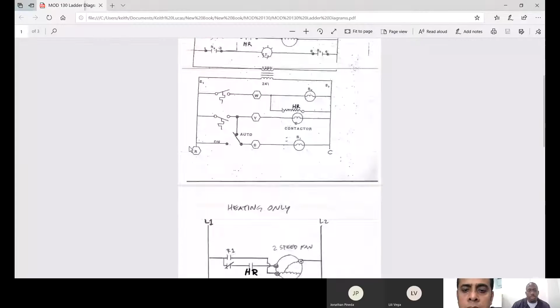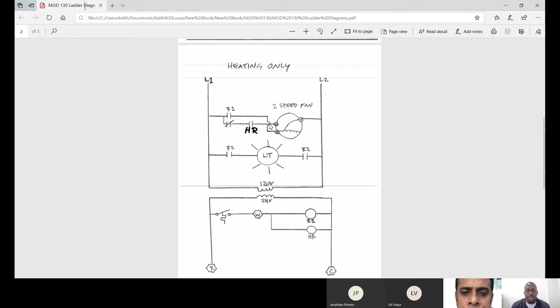So this was the diagram we were working off of last time. We had our low speed connected. We had the little red light connected to simulate the gas heat, and we were only using W, which is the heating circuit on the thermostat. And once W is energized, our 24 volts will pass through our temperature switch, which is inside of the thermostat, and then it's going to energize the relay 2 coil and the heater coil. So the relay 2 coil, once those contacts are closed, that's what energized our light. And then once this heater relay contact was closed, that's what energized our low speed fan.